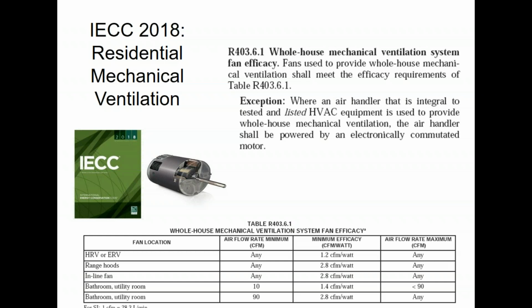John is typing in a question: is ventilation required for furnace or boiler replacement? So just to be clear on two things. One, right now I'm talking about fresh air for the home, not combustion air. Combustion air is going to be a separate requirement that may or may not be needed for your furnace, depending on whether it's separated combustion or not. Right now, what we're talking about is just the ventilation air, and I assume that's what John's also asking about. So what he's asking about is, if I do a furnace change out, am I going to have to put an outside air duct in?